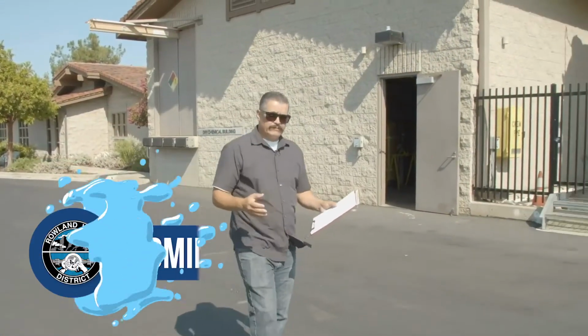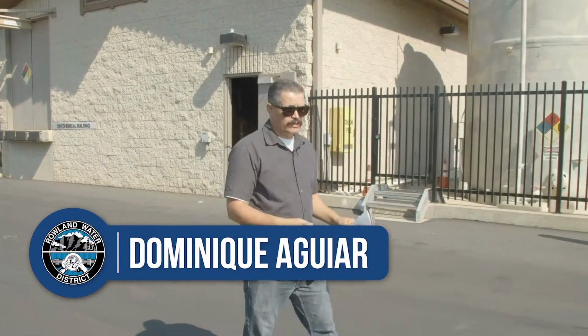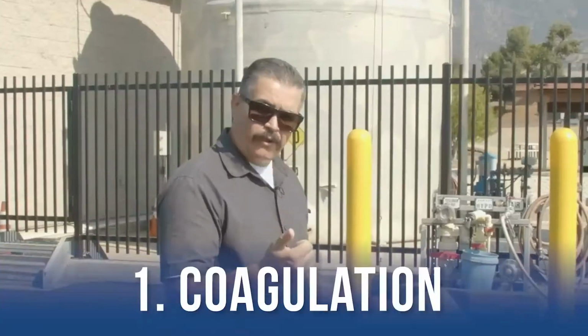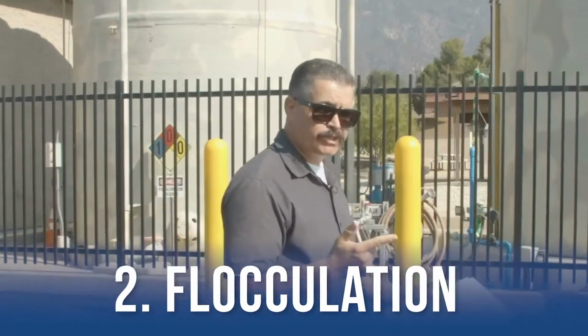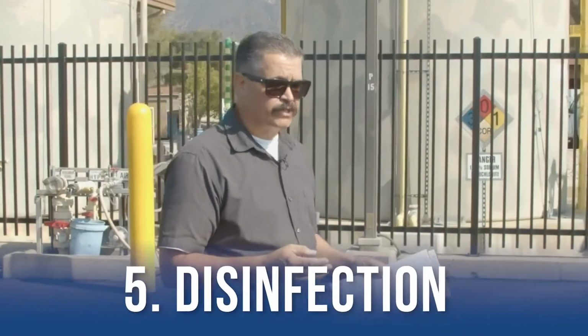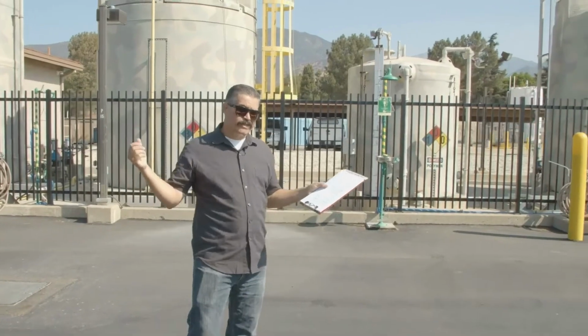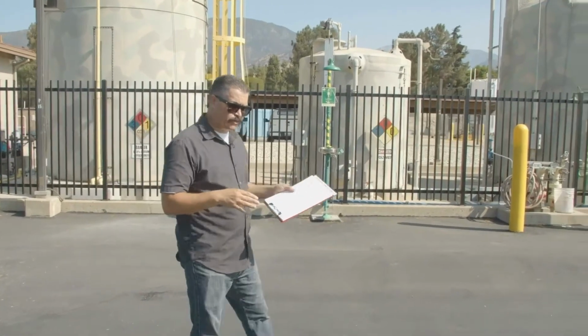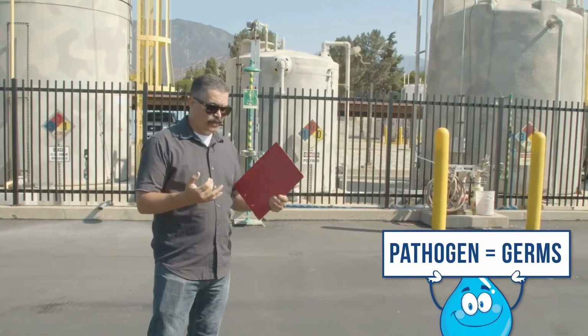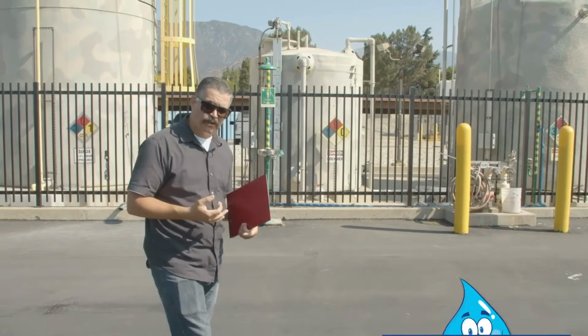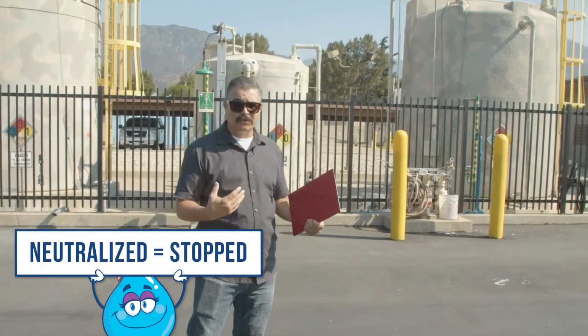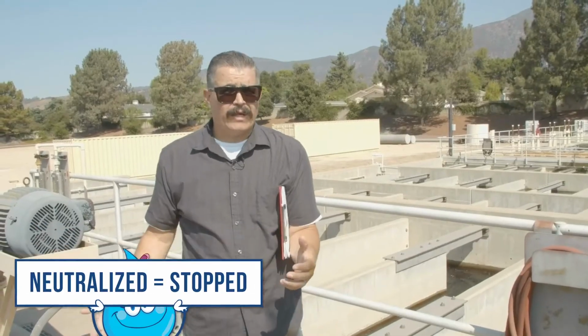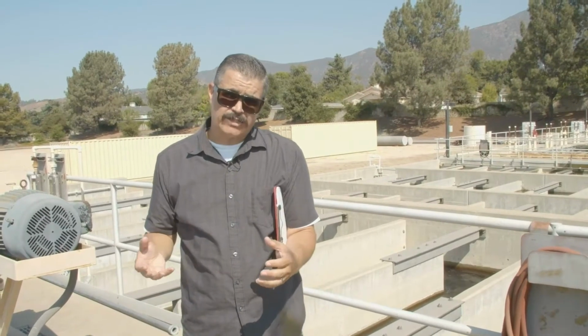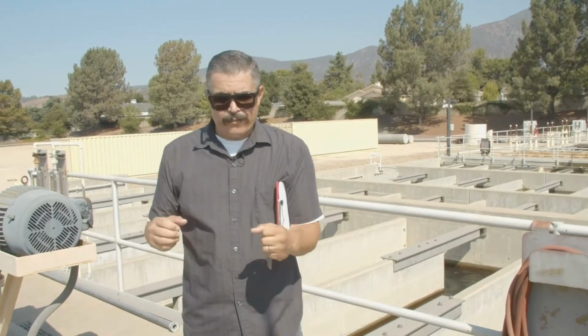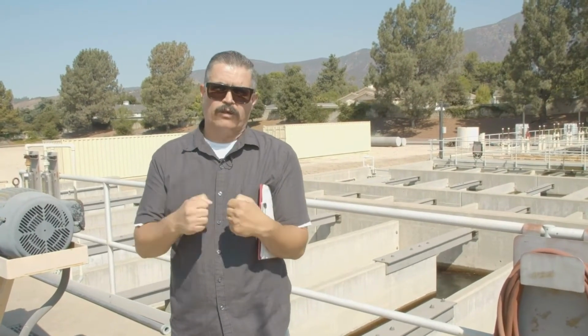In describing the stages of a conventional treatment process, there's roughly about 5 stages: coagulation, flocculation, sedimentation, filtration, and disinfection. Our goal is basically to disinfect that water and make sure that any pathogens or any viruses that exist in that water are neutralized or removed altogether. This is what we call the coagulation process. The coagulation process, our goal for that is to basically merge the chemical with the water molecule.